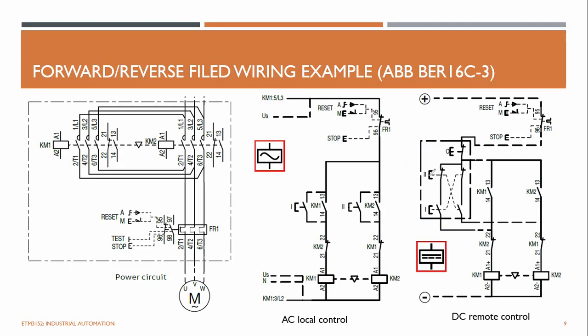So if you press this one, pressing this one disconnects this one and closes this one. So the current will flow from here to here, through here, and like that. And the KM2 will energize and the KM2 will self-latch. And now the current path will be diverted from here. And even if this guy releases, it is self-latch and keeps continuing and KM2 is running.